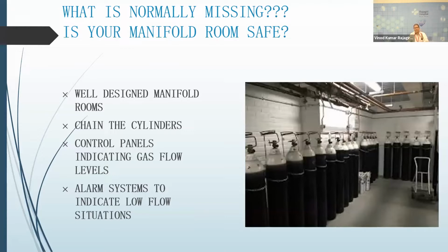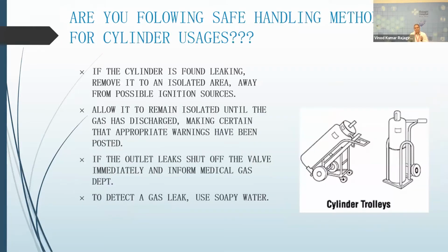So providing a spacious area which is clear, away from any hot or combustible positions, and having control panels and alarm systems is also missing in many places. Another point to be talked about is the safe handling of these cylinders. D-type or B-type cylinders, whichever they are, if they are not handled properly, you will get into an accident wherein it becomes a source of leakage of oxygen from these cylinders.